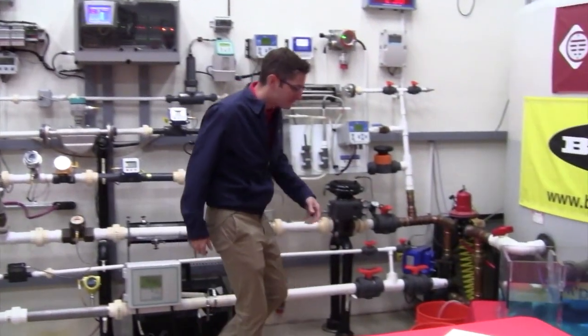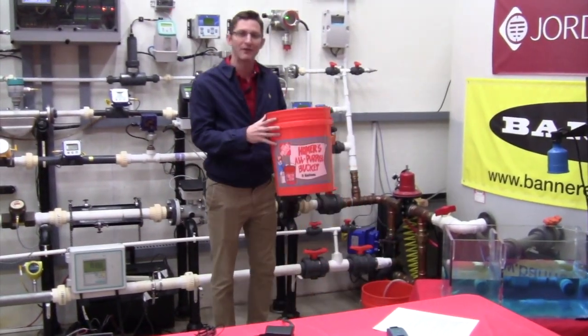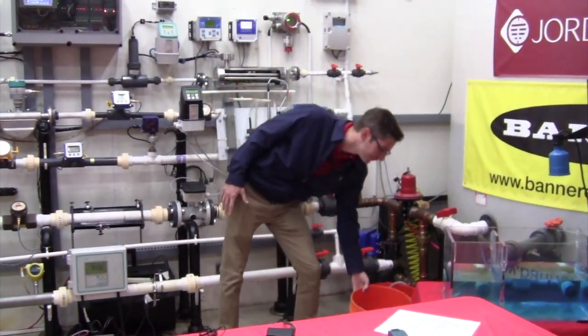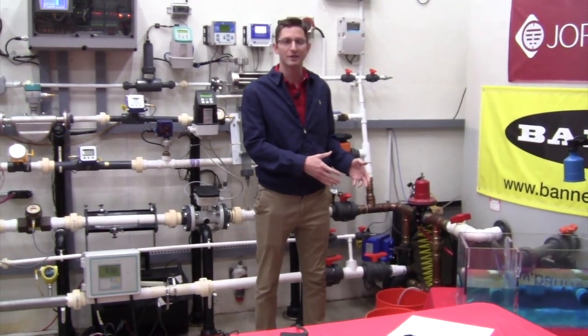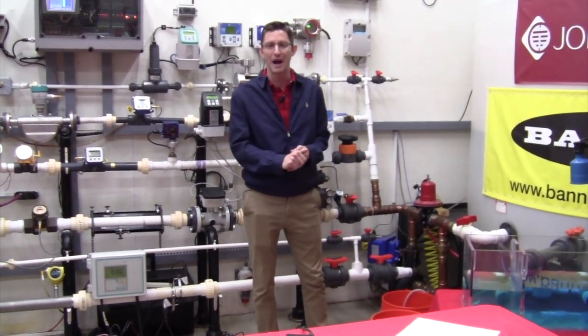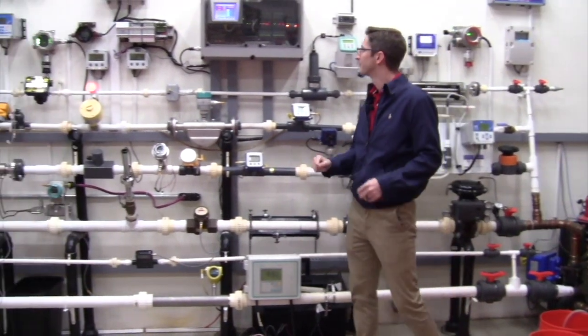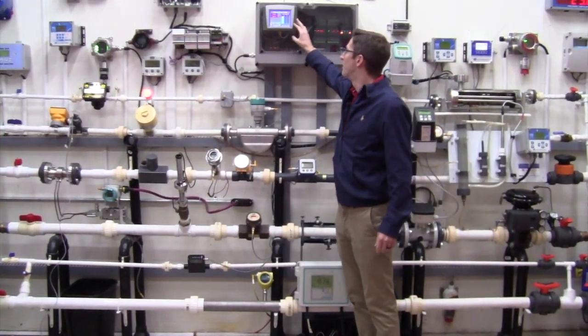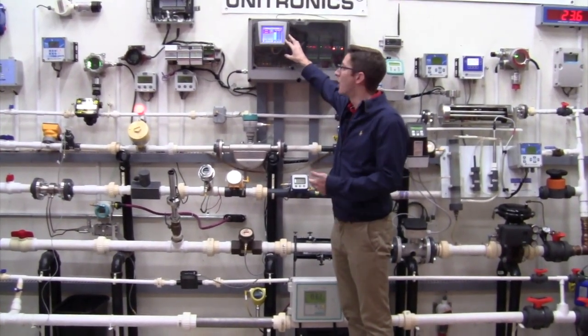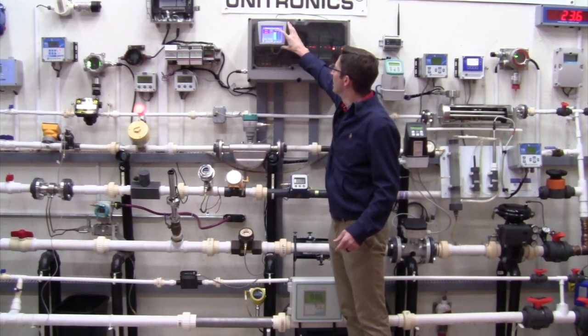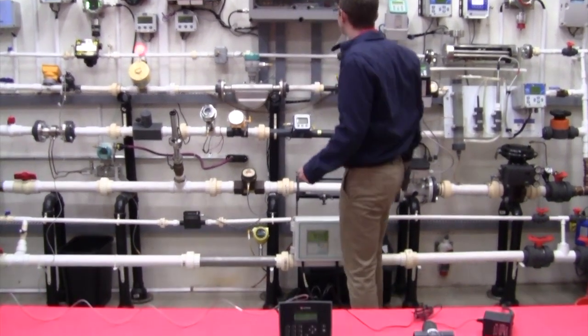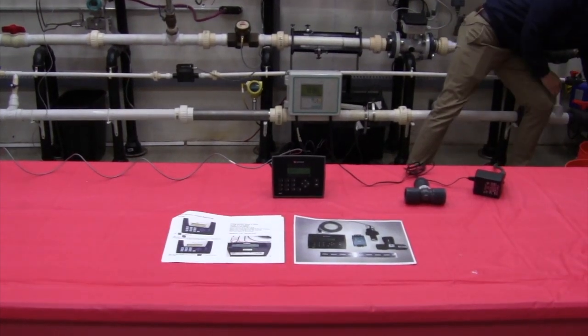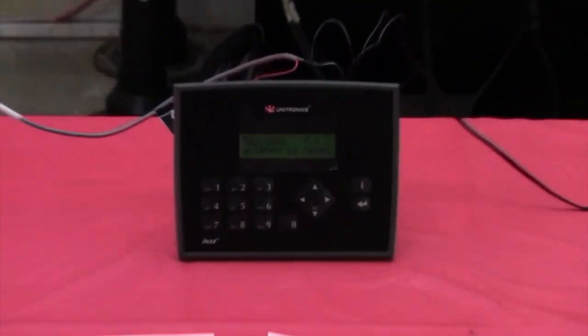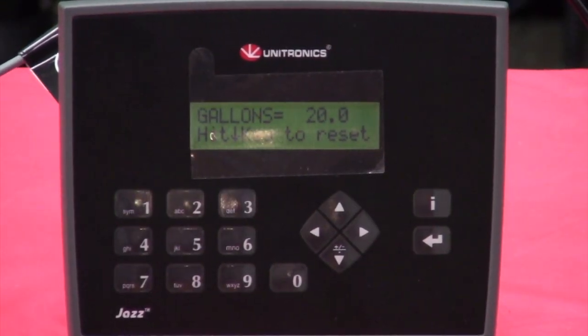Final step, we've got a 5-gallon bucket that we're going to fill up. Once that 5 gallons is completely full, then I'll show you the math that needs to be done for a calibration. So I'm going to come here to our PLC. This is how we turn our pumps on and off in the flow lab. So I hit my pump on, come over here and open the valve. And now we're beginning to flow into our bucket.